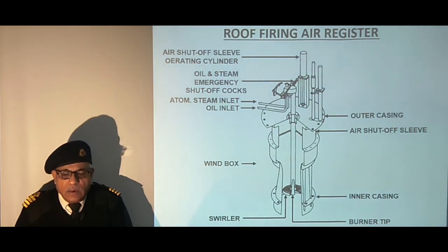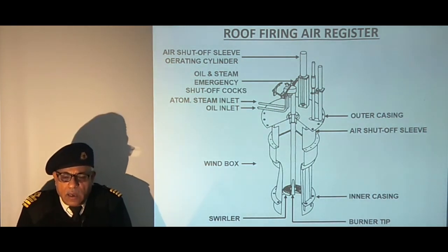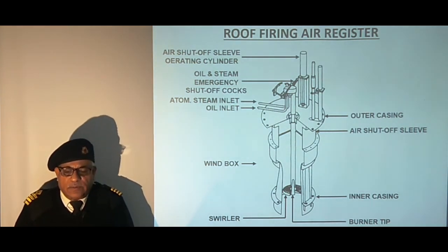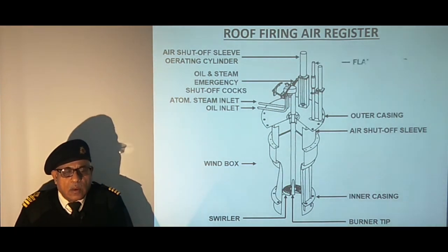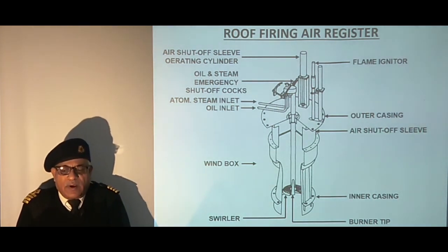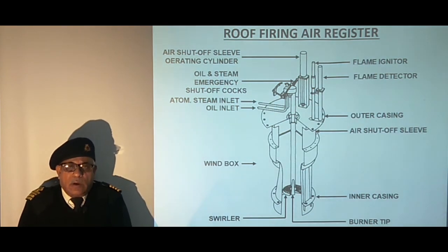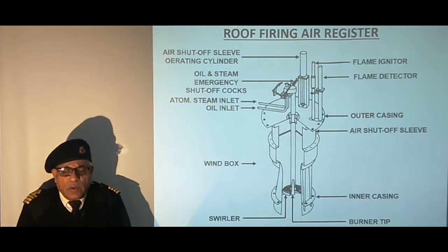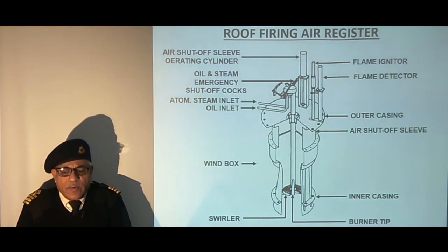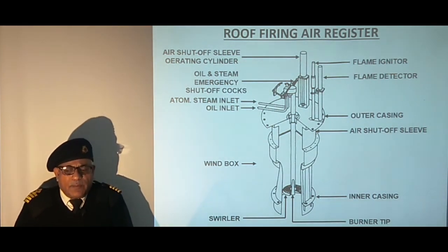The swirler provides rotation to the secondary air for intimate mixing with fuel droplets. Igniter and pilot burners are used to light up the furnace, and the flame is monitored by the flame detector. The igniter, along with the pilot burner and flame detector, are moved inside by the pneumatically operated cylinder for ignition and brought back out to prevent damage from the intense heat of the main burner. This completes our study of combustion in boilers and air registers.